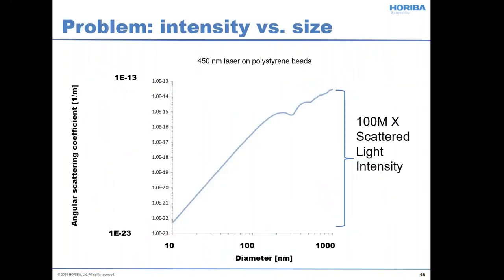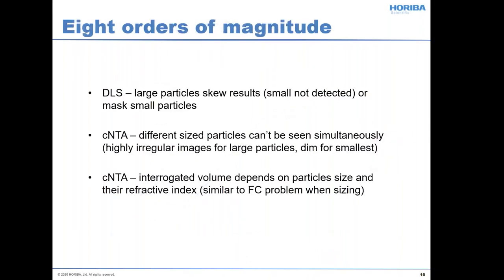Now it's time to move into some of the bad news. If I look at scattered intensity as a function of particle size, I see about eight orders of magnitude variation in scattered light with a two-order-of-magnitude variation in particle size. In DLS, you're going to see a much stronger effect from the larger particles, which will tend to mask the small particles when looking at distributions. With classical nanoparticle tracking analysis, if you set up your system for one particle size, you don't get useful data on other particle sizes. There is also an effect where your observed volume depends on particle size and refractive index, leading to varying effective volumes.